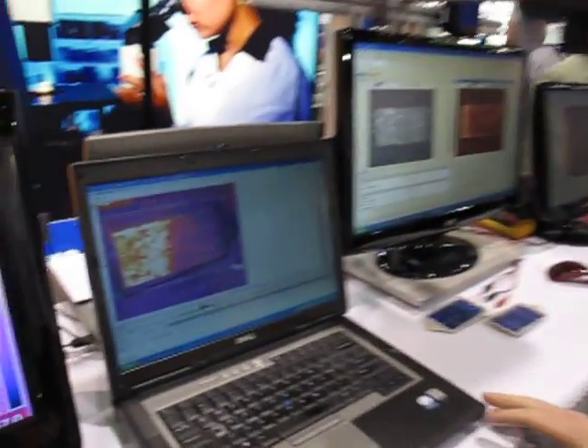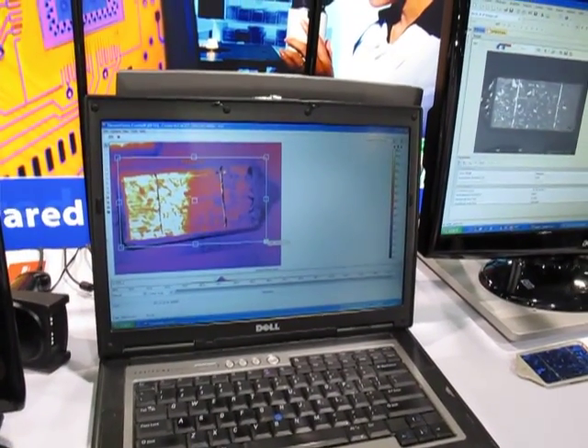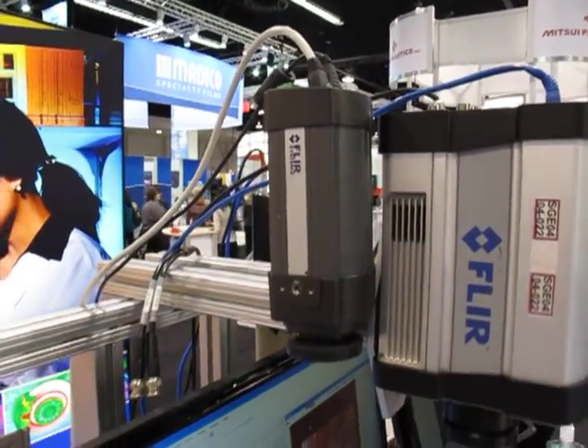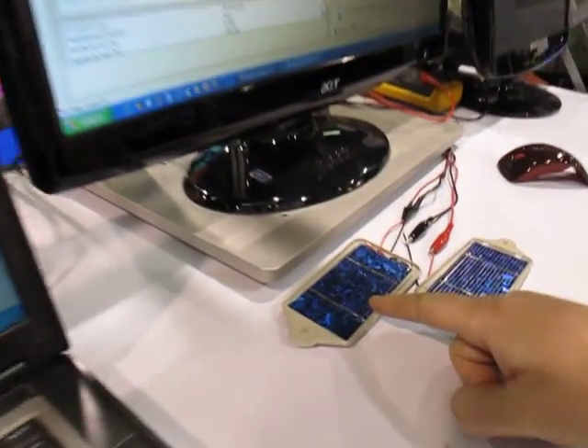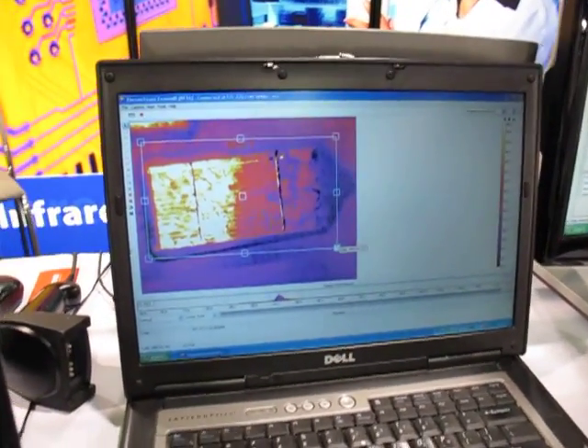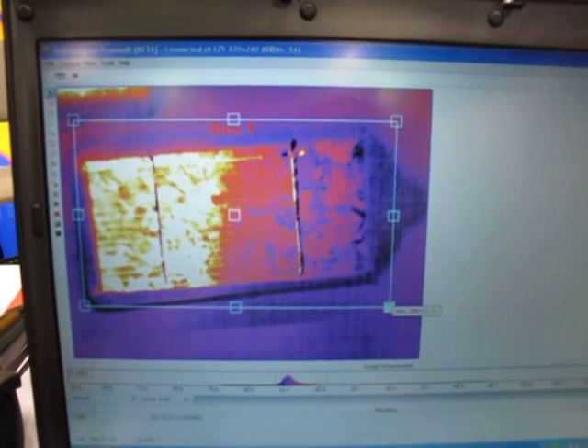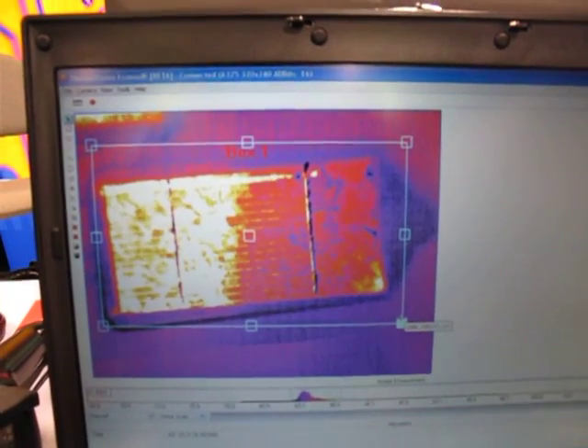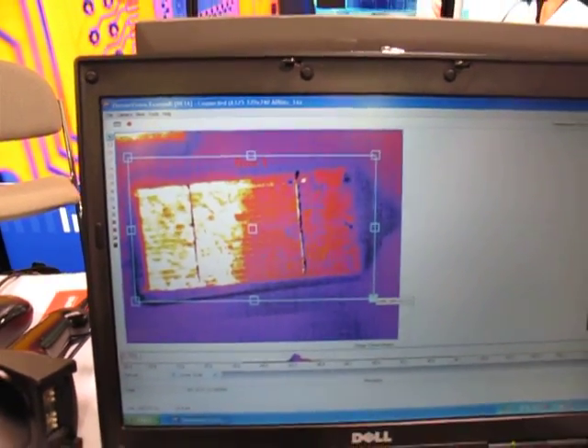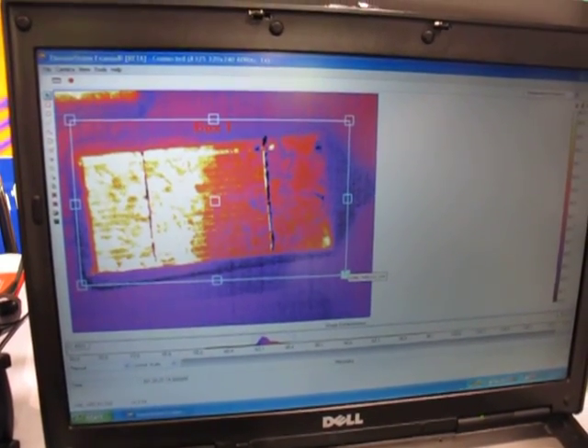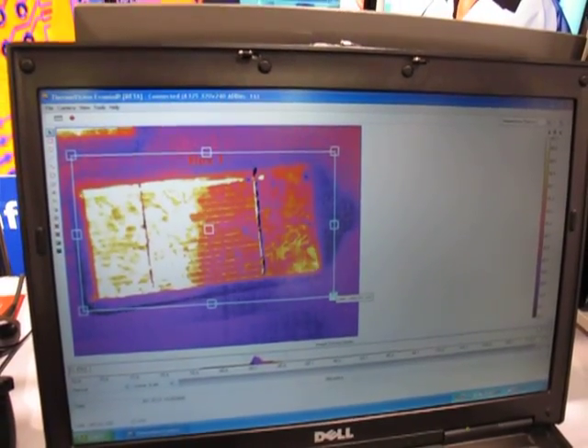Then we move on to the high-end R&D systems. The first one is to show reverse bias for solar cell testing. It uses an A325 camera, looking down at this solar cell right here on the table. The software that we're using is our Examiner Max software. We'll excite the solar cell with reverse bias, and you start to see the corner heat up down here. Basically we're wiring the solar cell backwards — in areas where we have defects, current starts to flow and you see it start to warm up. And that's among the simplest tests performed for solar cells.